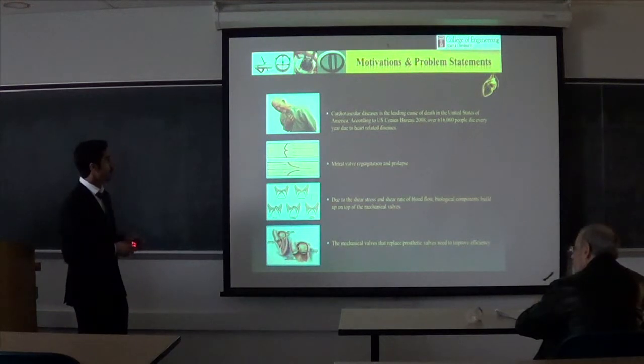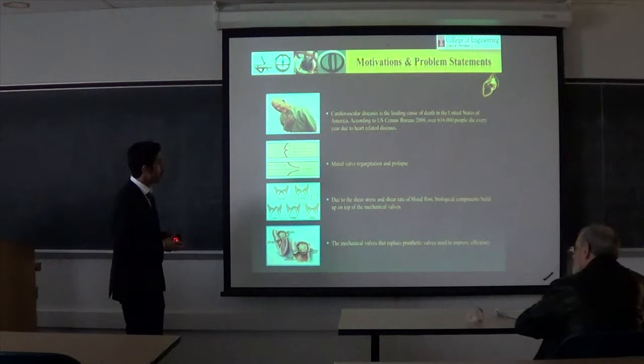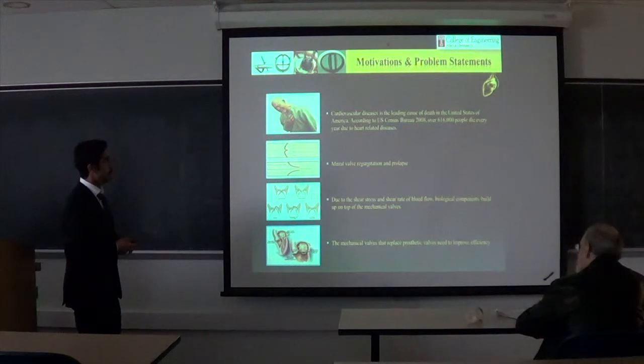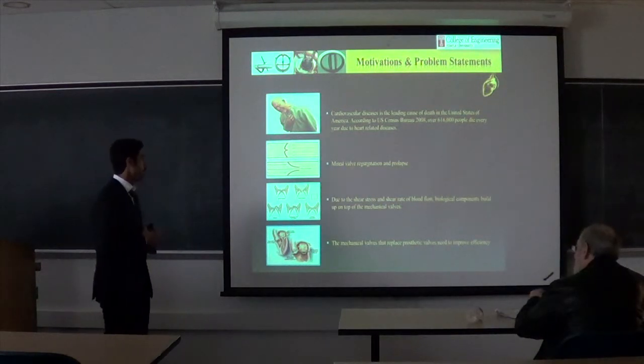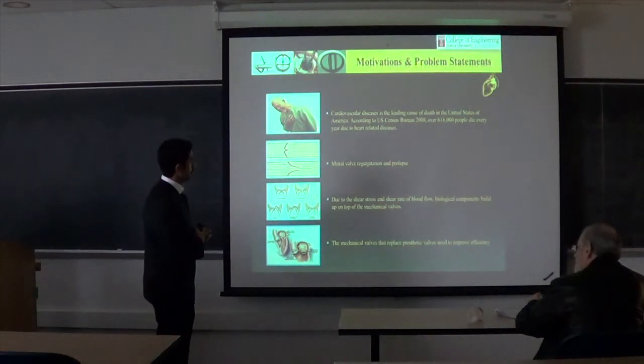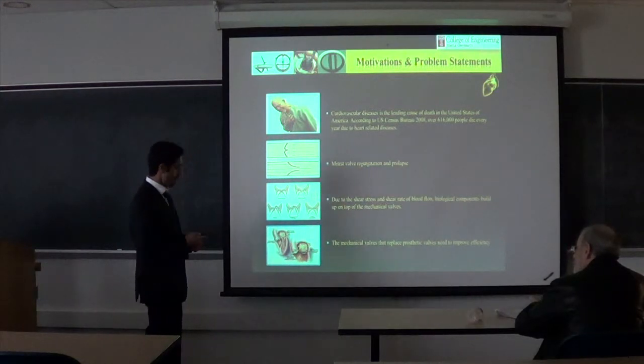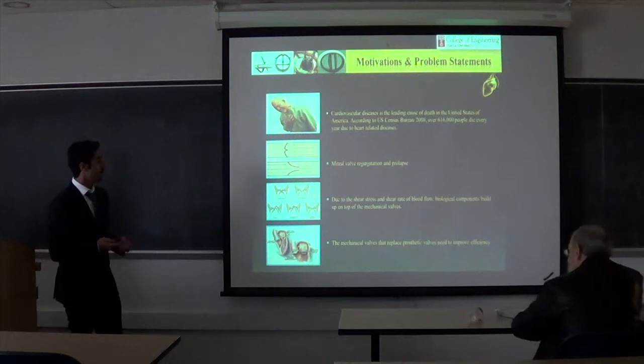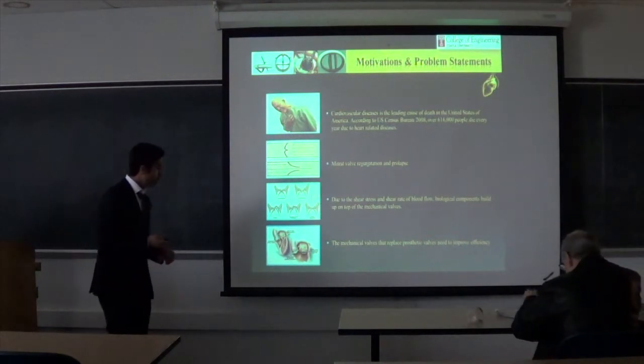Patients are replacing their valves with mechanical valves. However, because of the shearing stress and the shearing rate of the blood flow, biological components build up on the materials of these mechanical valves. So we decided to design a device that will be able to test the build-up.